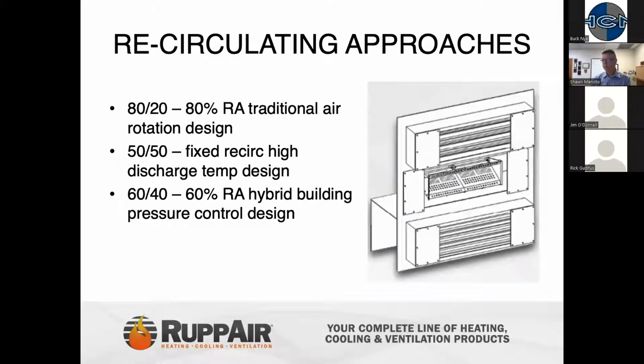So the recirculating approaches: 80-20, 50-50, 60-40. What does this all mean? So the 80-20, you guys may have seen that terminology in the industry in the past, but the 80% refers to the maximum amount of return air that can be brought through the system. So over to the right-hand side here, we see an illustration of a return air system. This burner area we're looking at here in the center is designed for consistent 20% outside air. The balance of the air is either going to come through a fresh air bypass damper above to bring in 80% here, or a return damper coming back from the building 80% through here.